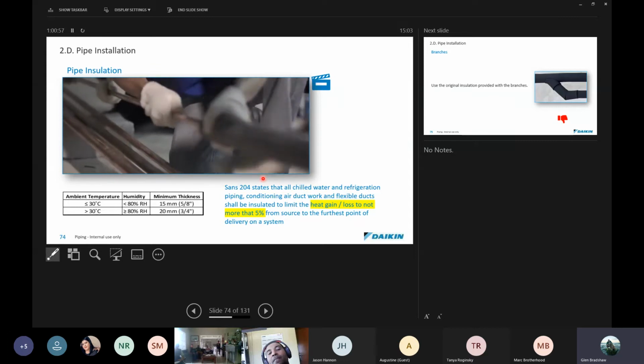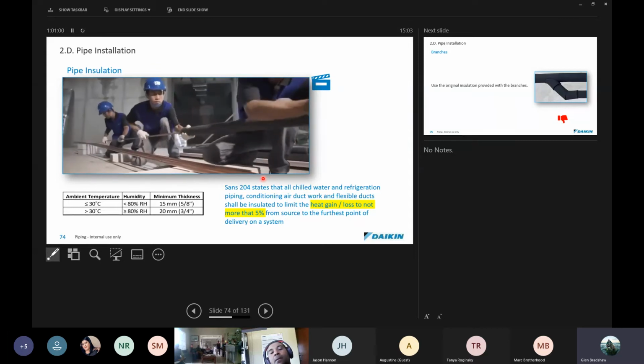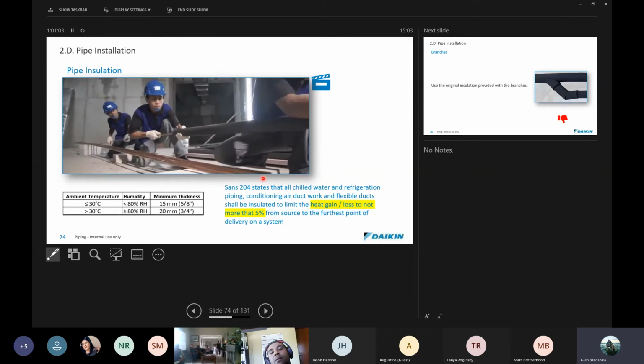Here's a video of the guys installing the insulation. Make sure when you're installing the insulation that it's not torn, and also that you don't over tighten the taping on the seams on the joints. You don't want to squish that insulation down, because there you create an area of loss. So taping must not compress the insulation, but more just join the sections. And I do see in some of the guidelines that they actually recommend gluing the sections as well.